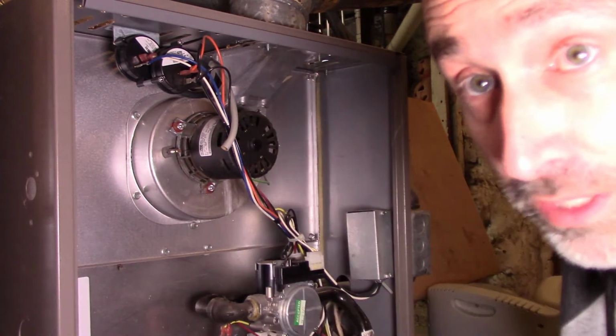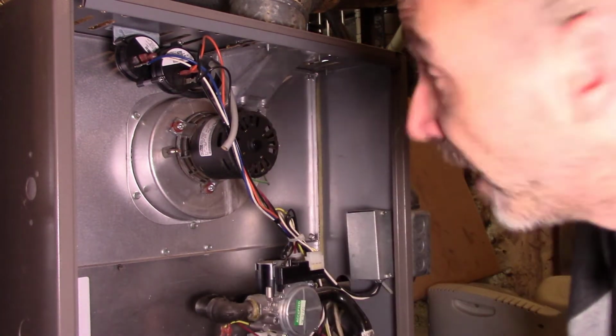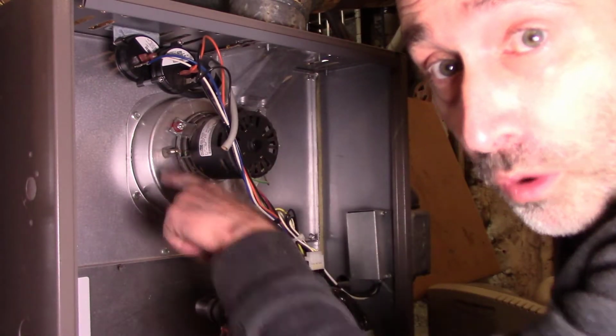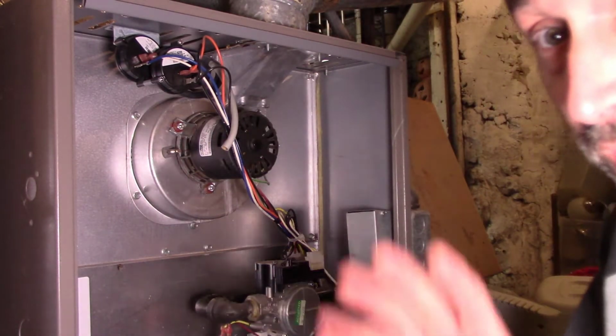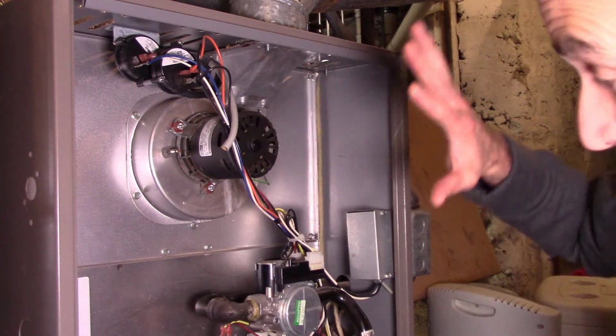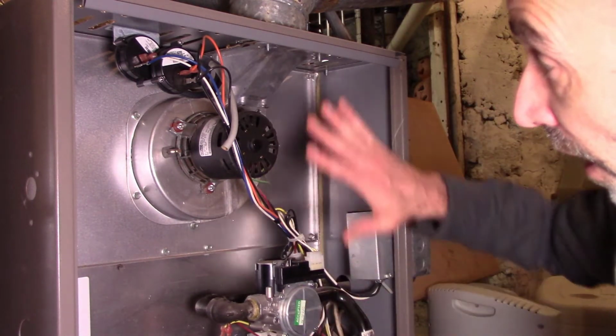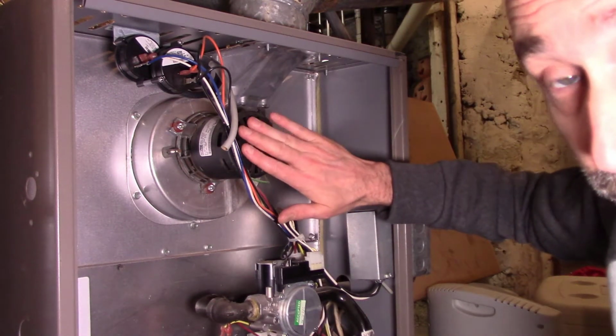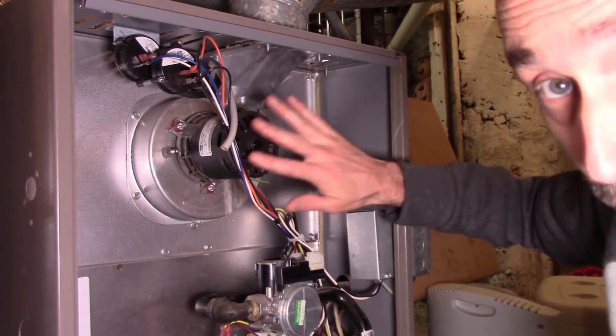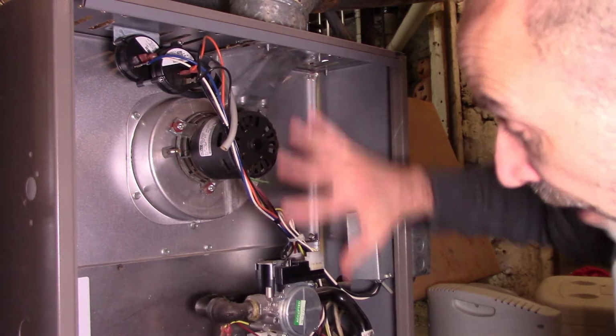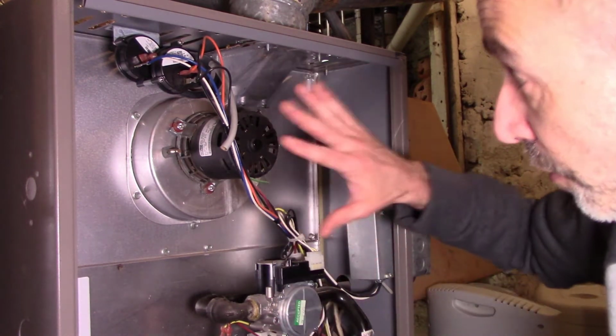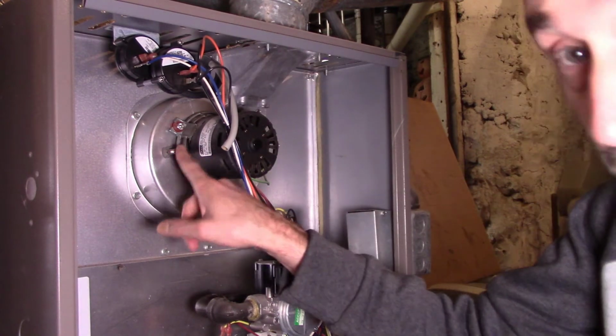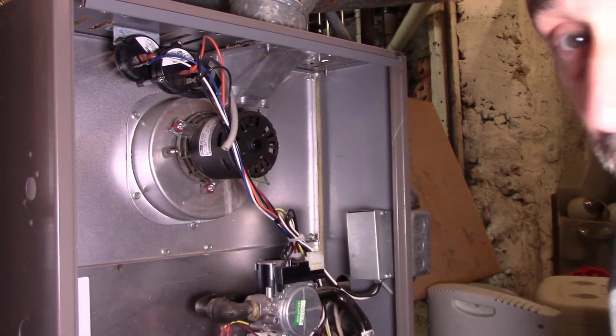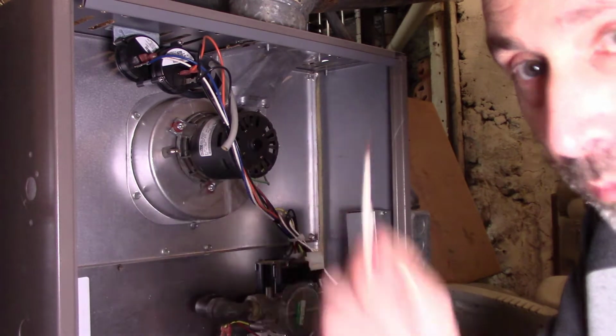And believe me, from experience, I've woken up in the middle of the night and it was a clogged inducer port that kept this from firing. And again, all I did was I watched the furnace start up. I listened and saw the inducer motor start, but yet nothing else fired. And that usually is a telltale sign that your inducer port is just clogged up with some debris and you just need to clean it out with a bit of wire.